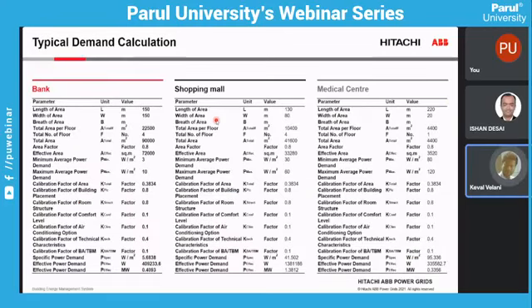Here you can see a typical demand calculation for a bank area, shopping mall and medical center. At the end of the procedure for the power demand and load flow of the power demand, you find the wattage per square meter. What is the wattage per square meter in a bank? This is 5.6 watts per square meter in a bank, and you have to calculate the power demand. In a shopping mall, it is 41 watts per square meter. In a medical center, it is 95 watts per square meter.